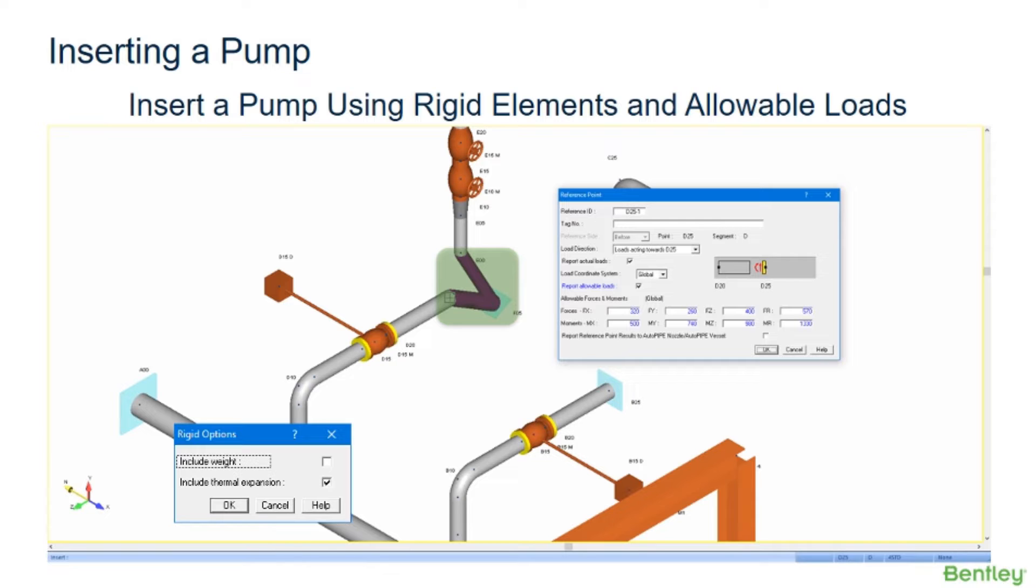This will help account for nozzle thermal movements automatically by specifying a temperature for the rigid piping representing the equipment. This feature is very useful to create a comparative load ratio report for any nozzle or connection to a vessel or rotating equipment respectively, which has manufacturer-defined limits.